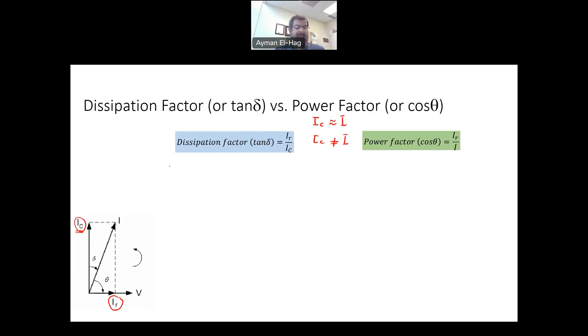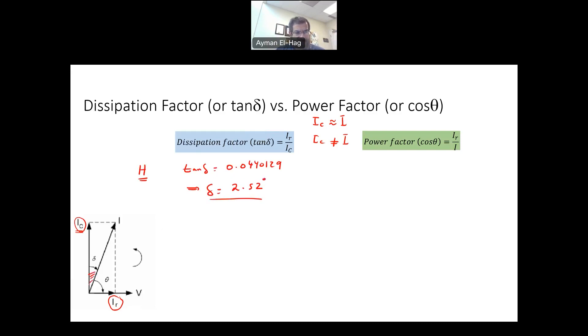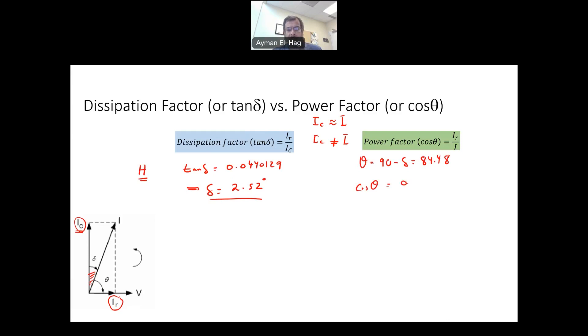Let's use the same numerical values. For the healthy insulator, the dissipation factor — tan delta — was equal to 4.4%, or 0.0440129. From this, delta, the tan inverse of this value, equals 2.52 degrees. Theta, on the other hand, is 90 minus delta, which equals approximately 84.48 degrees. So cosine theta equals 0.0439, and so on. This is why we have similar values — cosine theta is close to 90 and delta is close to 0.